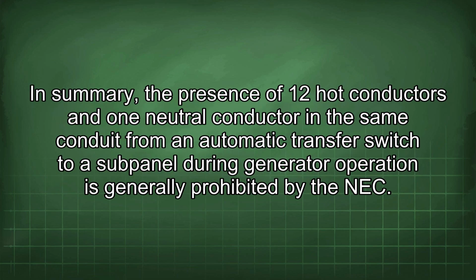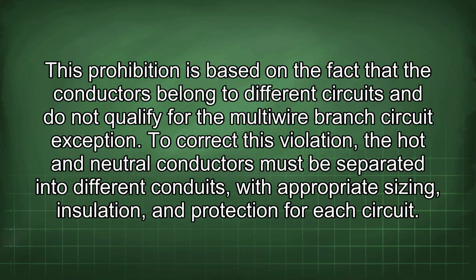In summary, the presence of 12 hot conductors and 1 neutral conductor in the same conduit from an automatic transfer switch to subpanel during generator operation is generally prohibited by the NEC. This prohibition is based on the fact that the conductors belong to different circuits and do not qualify for the multi-wire branch circuit exception. To correct this violation, the hot and neutral conductors must be separated into different conduits with appropriate sizing, insulation, and protection for each circuit.